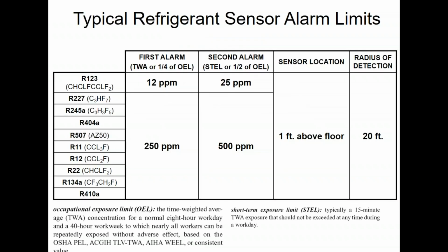The threshold amounts depend on the refrigerant you have, right? So I have a couple different amounts on here. For most refrigerants in a chiller room, 134A, R22, R11, R12, all of those guys, if I get to 250 parts per million, I need to generate an alarm, right? And that alerts the people that are in the space or people that would accidentally go into the space, hey, stay the heck out of here.